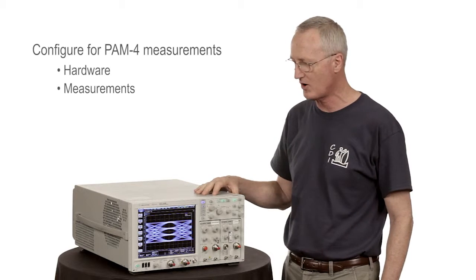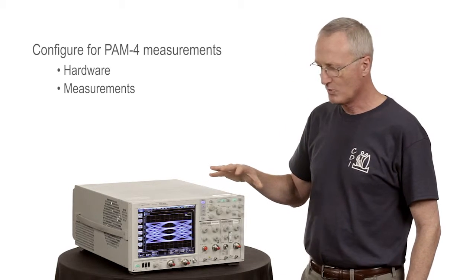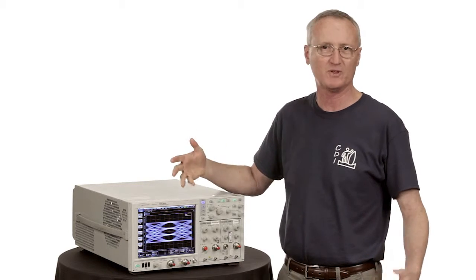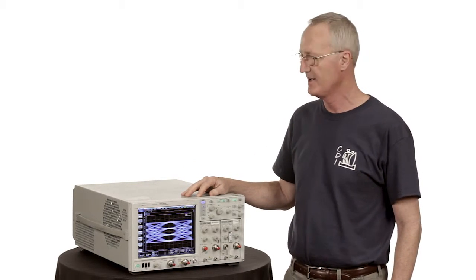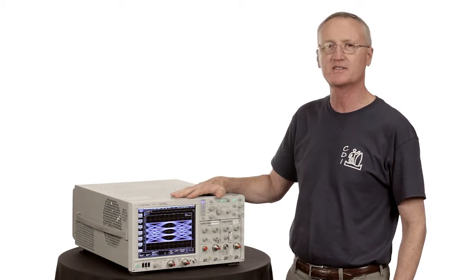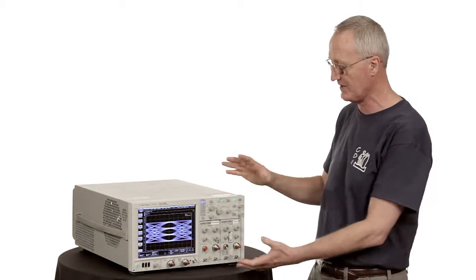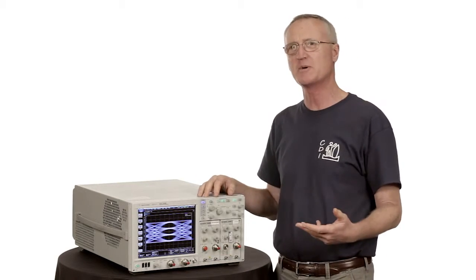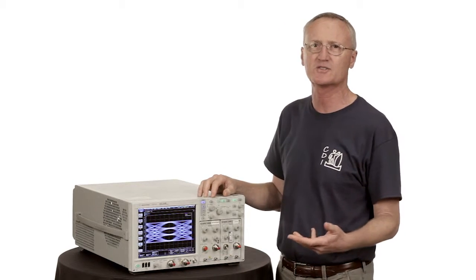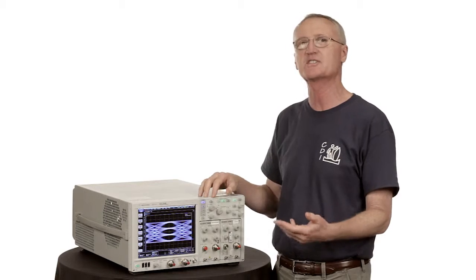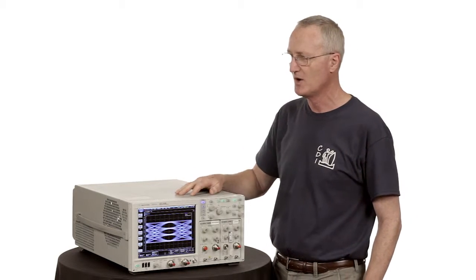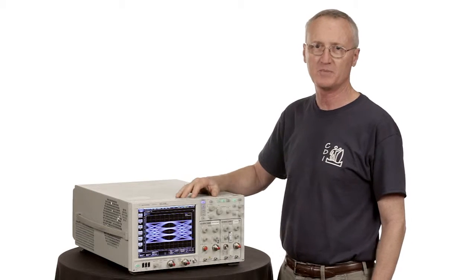So first let's talk about hardware. When we're configuring a scope to make a measurement, we often ask what bandwidth do you need to make a measurement? The DCA is capable of several different bandwidths depending on the plug-in module that you put into the mainframe. We've got plug-ins that do 20 gigahertz, 30 gigahertz, 50 gigahertz, even up to on the order of 80 gigahertz bandwidths. What is going to be appropriate for your PAM-4 measurement?